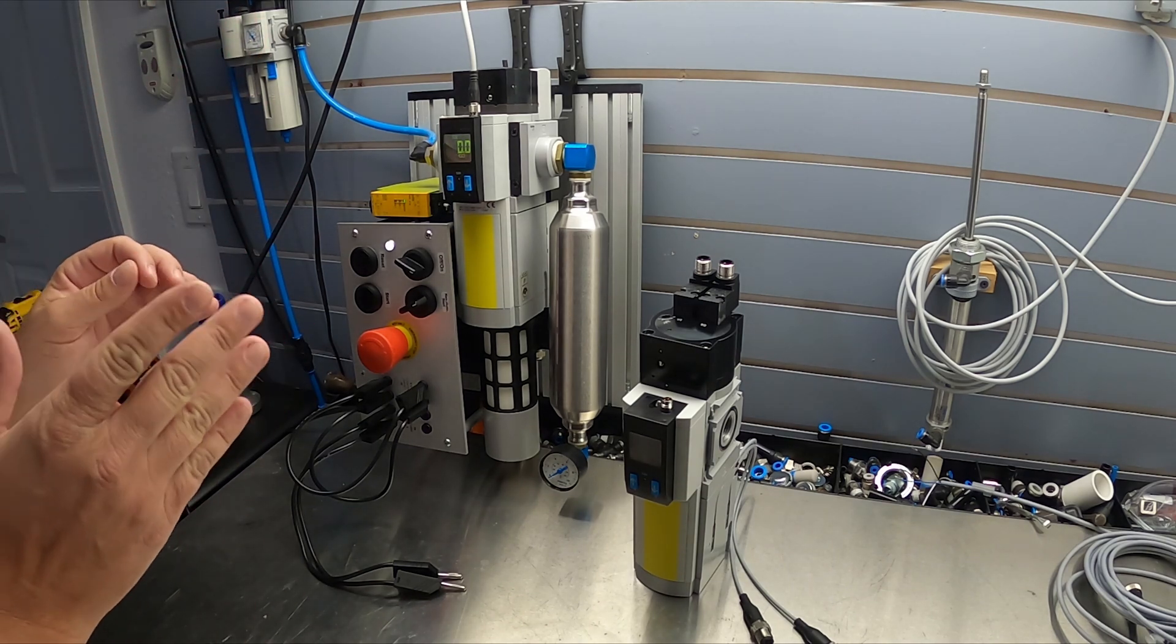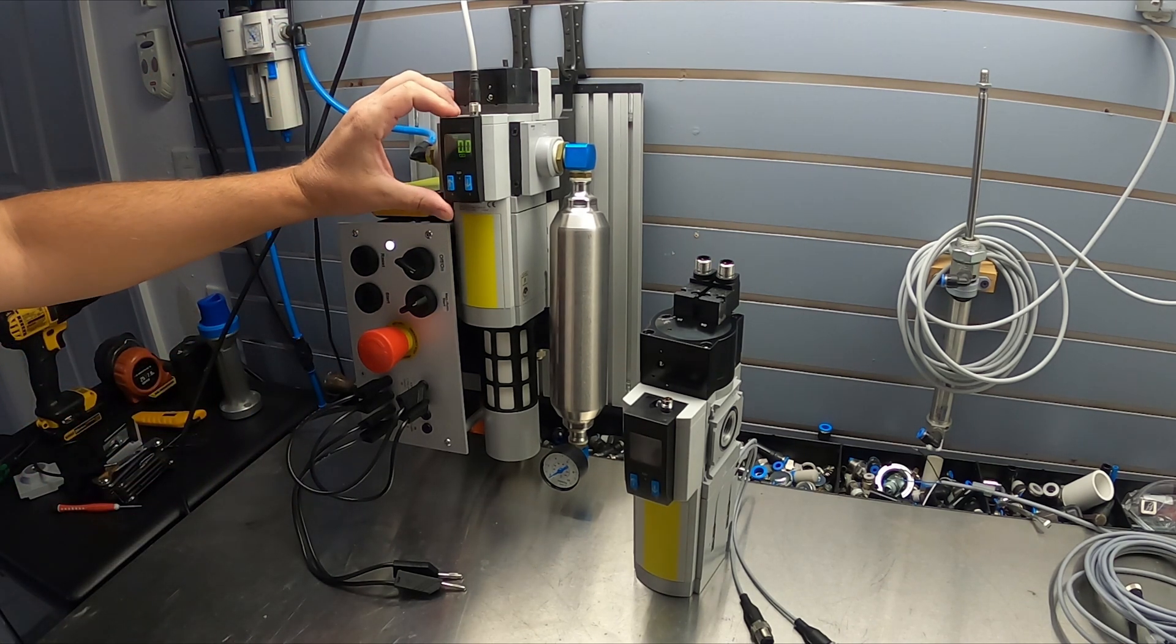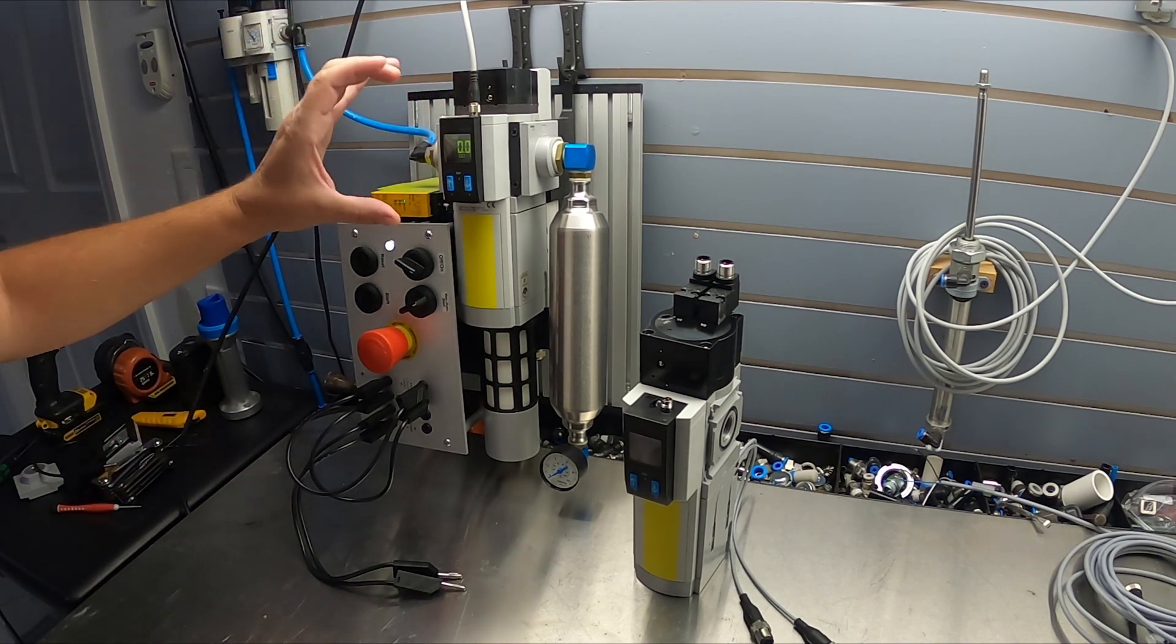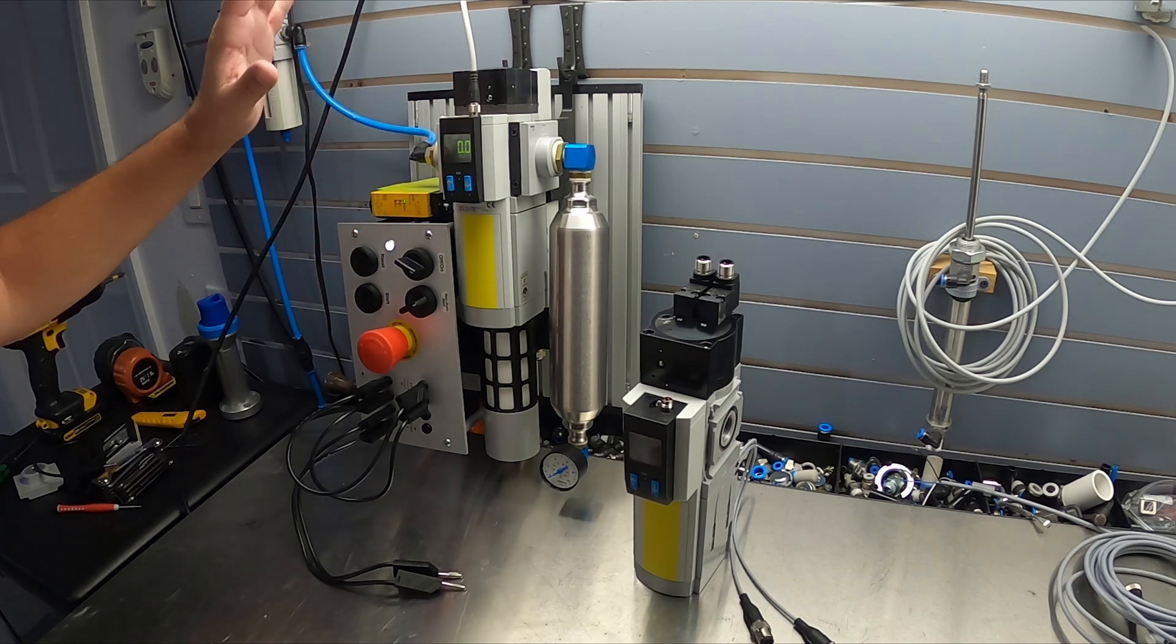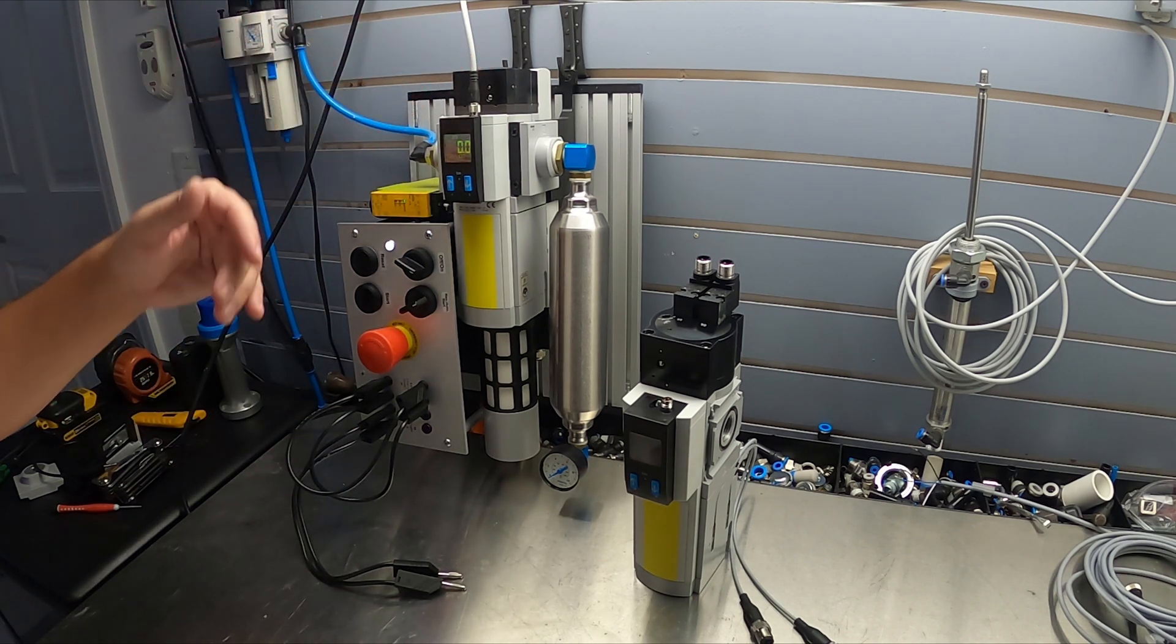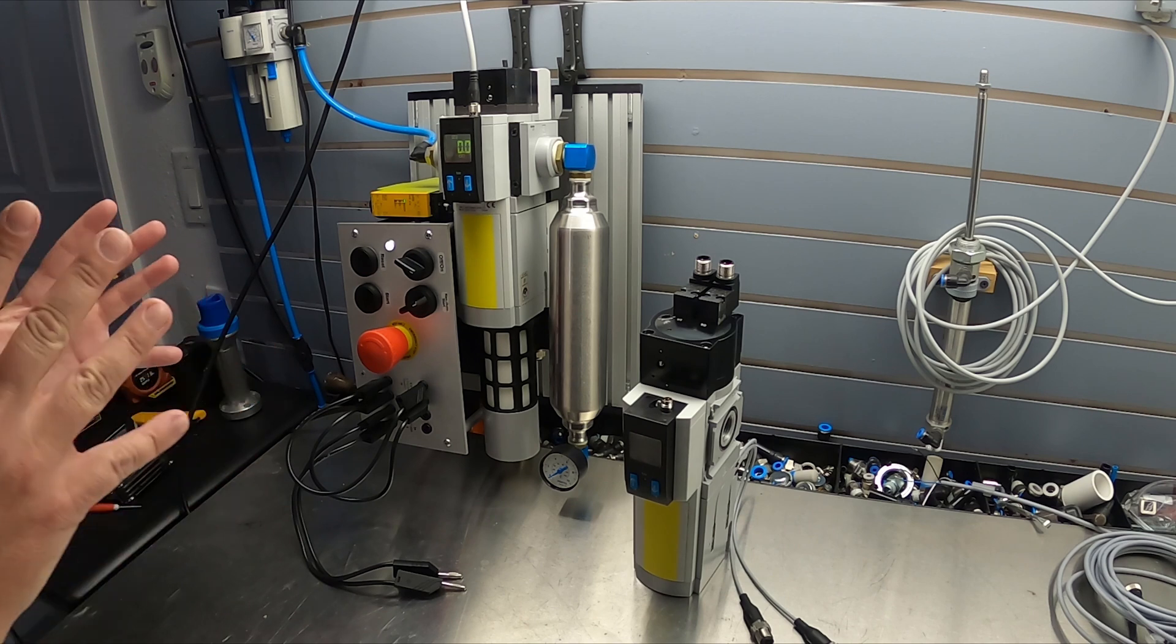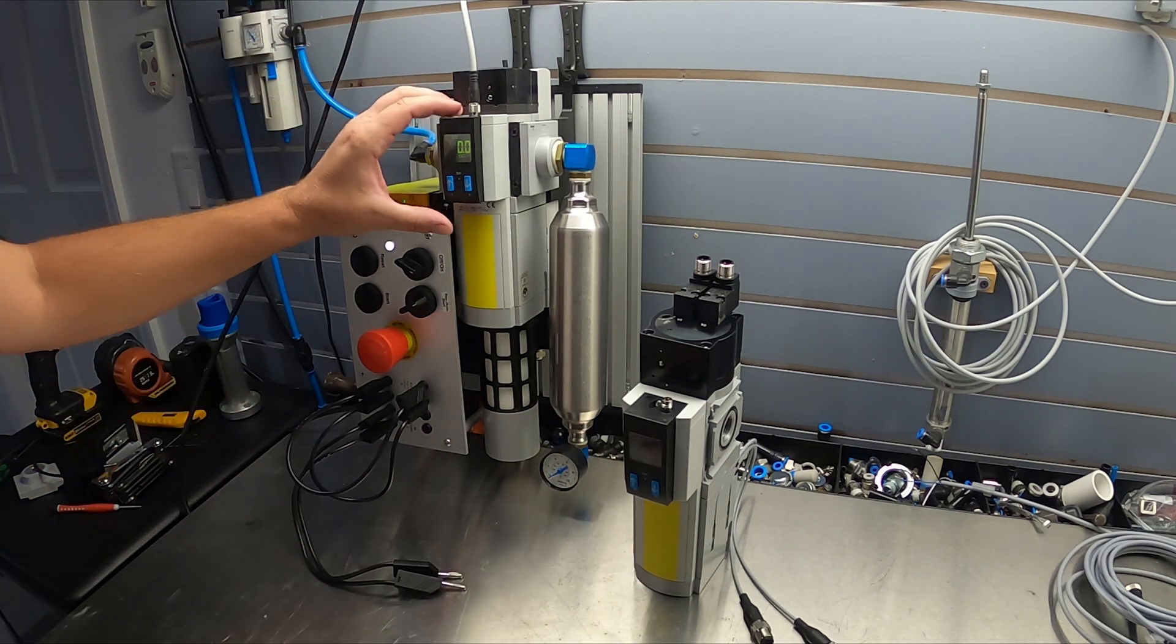So it's sitting in a mode right now where it's ready to go, it just needs the enable signals to get it going. If it sits in this mode for many, many hours, it will perform a self-check again once an hour. So if it's sitting without any enable signals on it but the power's on, it will do a self-check once an hour.